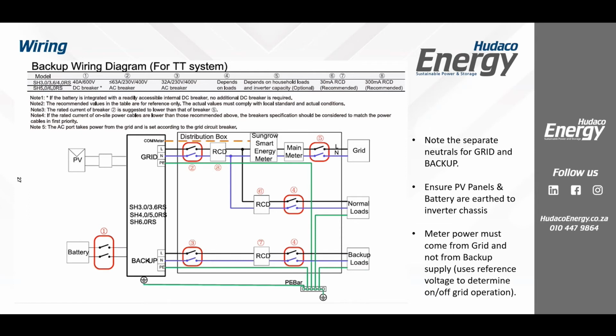Okay. Now this is for TT systems. Okay, in South Africa, most of the wiring that we use, especially in residential, is TT. So Terra, earth. Okay, if there's an earth spike there, then you're running with this type of a system. What's really, really critical, please. Okay, so you're using TNS on yours, hey? Okay. Often we see TNS often in commercial buildings as well. If you look in the drawing, in the installation manuals, there is a TNS as well. You can use the same thing for that. You're just bringing earths from here too. Okay, so you're welcome to go that route too.